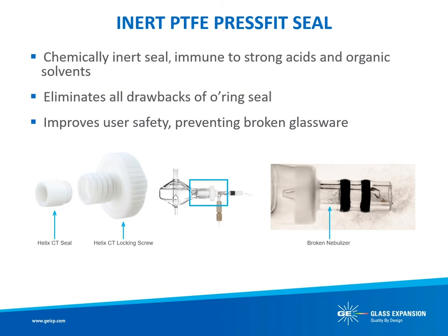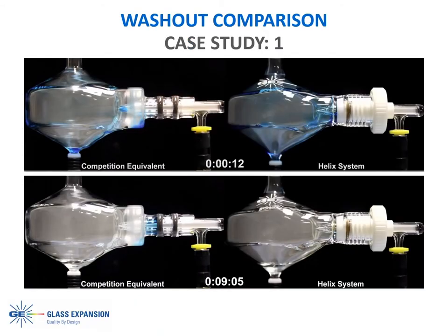There is also no need to worry about changing O-rings or nebulizers getting bonded to the O-rings. The replaceable seal of the Helix CT interface is made from PTFE, chemically inert and immune to strong acids and organic solvents. Helping to prevent broken nebulizers also improves user safety in the laboratory. In addition to maintaining consistent performance, you also want to minimize washout time. Do not be fooled by other O-ring free spray chamber designs or those older O-ring interfaces. Glass Expansion's Helix CT is truly the only zero dead volume interface available.